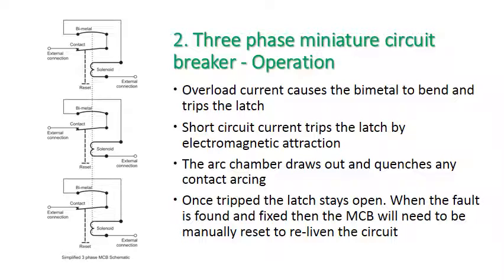But if the fault is more severe and short circuit current flows, then definitely you're getting enough magnetism for the solenoid to pull the mechanism open, and the circuit breaker will trip very quickly. If there's a lot of current in the fault, there will be a lot of arcing, and the arc chamber draws out and quenches any arcing to deal with that. Once it's been tripped, the latch stays open, and you will need to find the fault and fix it, and then reset the circuit breaker manually to re-liven the circuit.